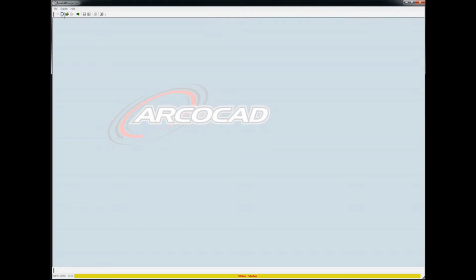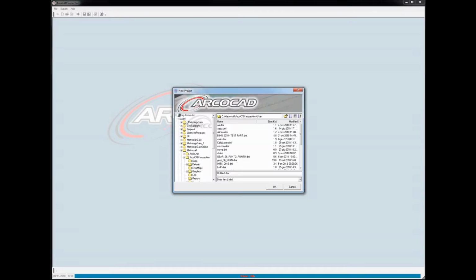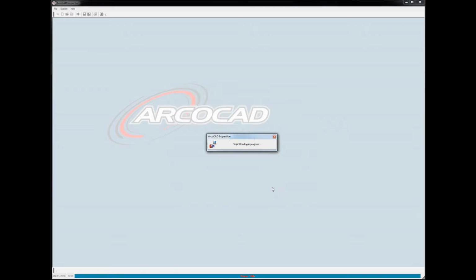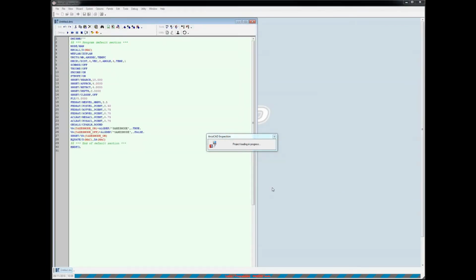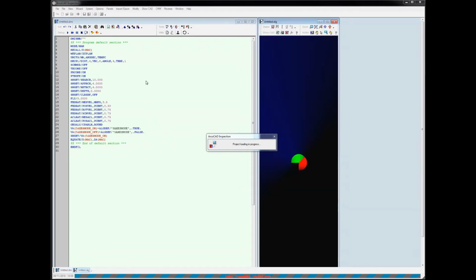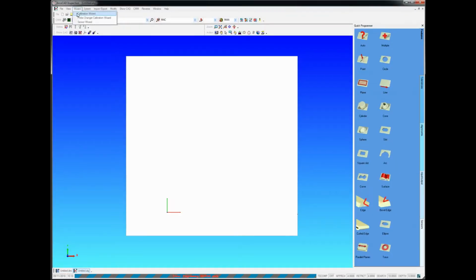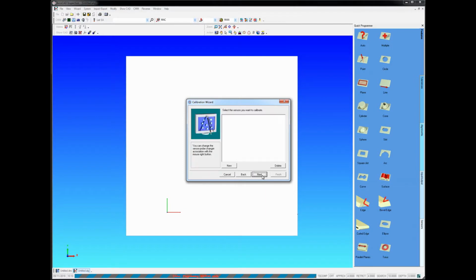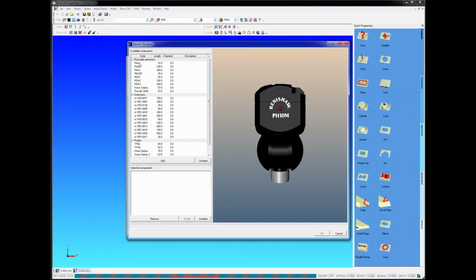The probe calibration is the mandatory procedure to guarantee accuracy. By calculating all the offsets among the different head orientations, Arco will make sure there is no error during the head rotation. Start the software and then run the guided wizard procedure, to define the probe, and run the calibration. The wizard guides the user into the calibration. It shows all the necessary steps in order to have an error-proof procedure.